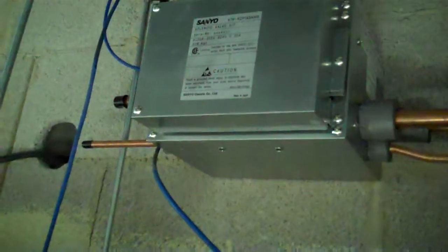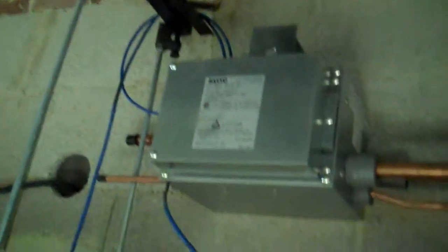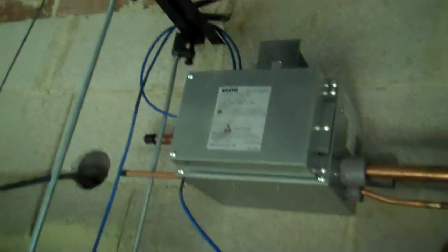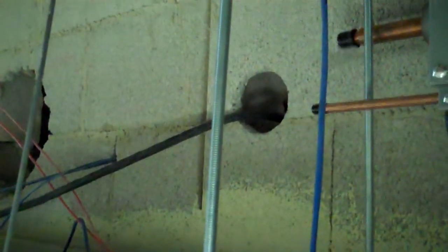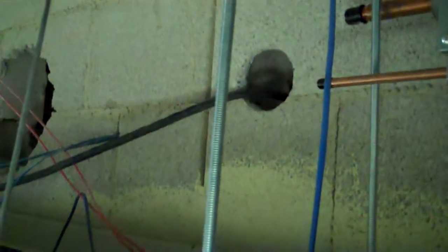So this is kind of like a parallel refrigeration system? Very much. Actually, what it'll do is rooms that are calling for cooling, as they're rejecting the heat from the space, they'll actually be rejecting that heat into rooms that are calling for heating. So what it does is keep the compressor from running at 100% capacity pretty much 90% of the time. As the demand for heating is there, rooms that are being called for cooling are actually being used to heat the rooms that are calling for heating, and vice versa.